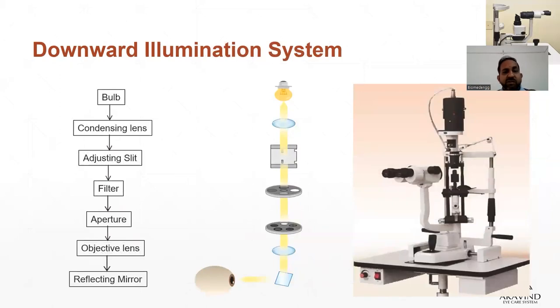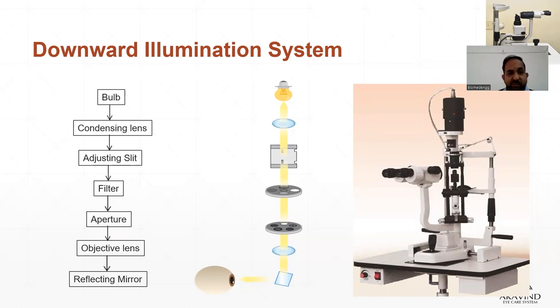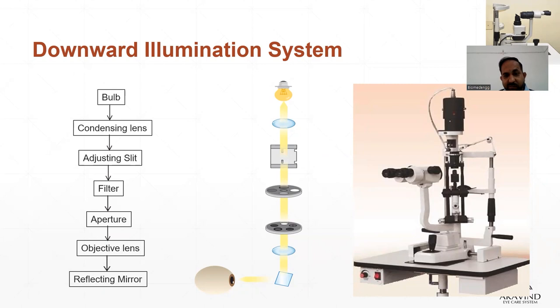Now let's see the downward illumination system. The downward illumination system is similar to the upward illumination system. One difference is that it uses a mirror kept at 45 degrees to direct the light into the patient's eye, as shown here.